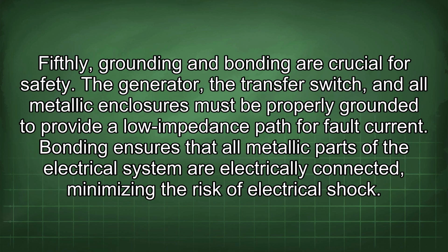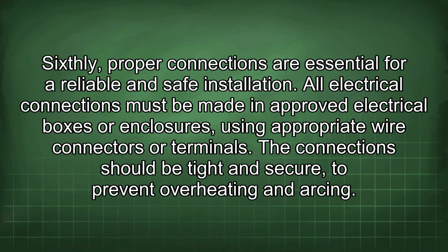applications. Fifthly, grounding and bonding are crucial for safety. The generator, the transfer switch, and all metallic enclosures must be properly grounded to provide a low impedance path for fault current. Bonding ensures that all metallic parts of the electrical system are electrically connected, minimizing the risk of electrical shock. Sixthly, proper connections are essential for a reliable and safe installation.